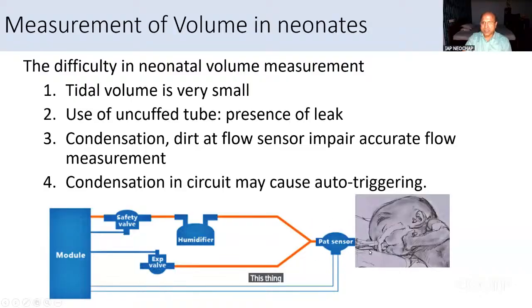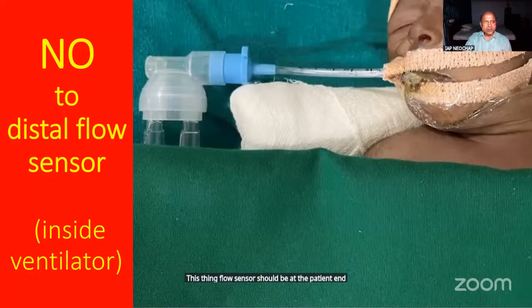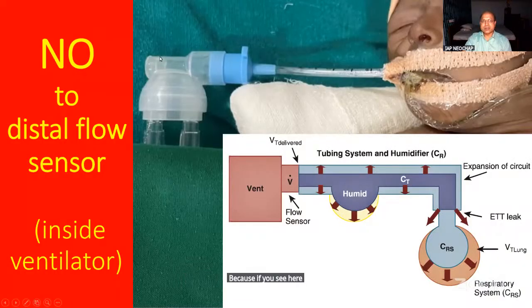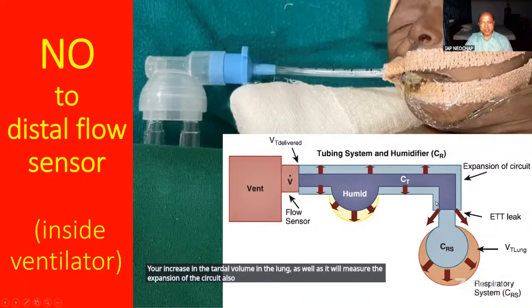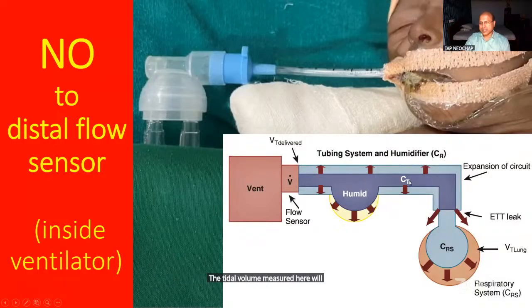The flow sensor should be at the patient end. Why? Because if you see here, this baby is not attached to a proximal flow sensor. So what will happen? The flow sensor is here in the ventilator. So if the ventilator is giving the pressure, it is increasing the volume in the lung. Apart from that, it is causing expansion in the circuit also. So the ventilator will measure both the increase in tidal volume in the lung as well as the expansion of the circuit. And nowadays we use disposable circuits, which are very compliant circuits.